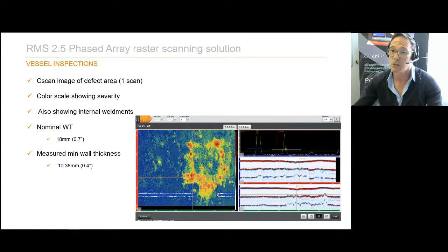So what we found is that the nominal thickness was 18 millimeters, 0.7 of an inch. And we actually measured the minimum wall thickness to be 10.38 millimeters or 0.4 inches. Quite great results. This is immediately very valuable data for the asset owner, and I think great data for a service company to present to his customer.